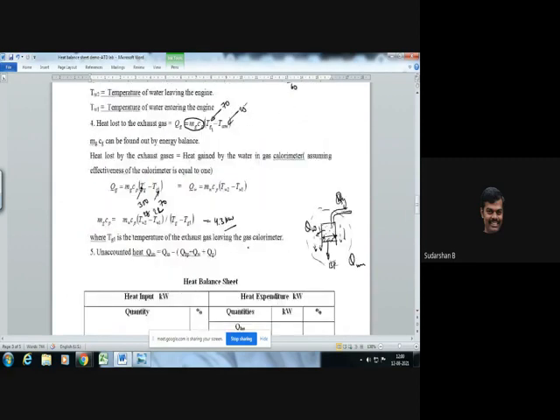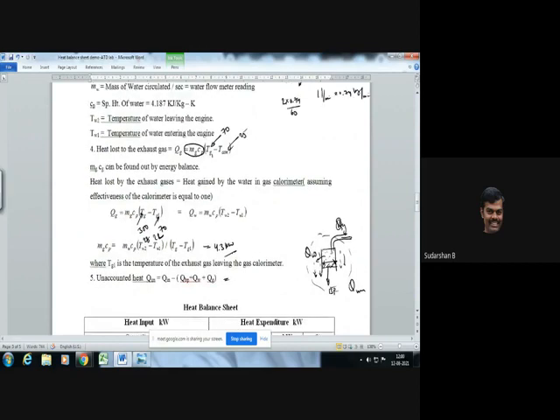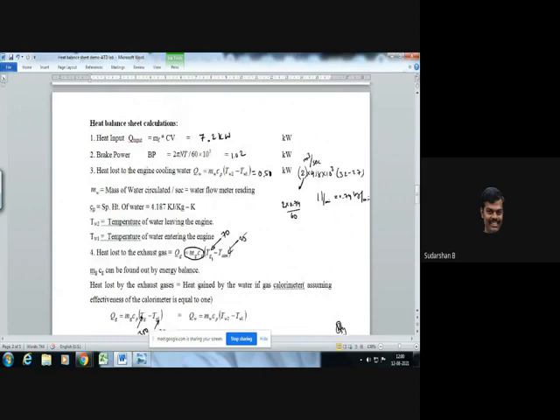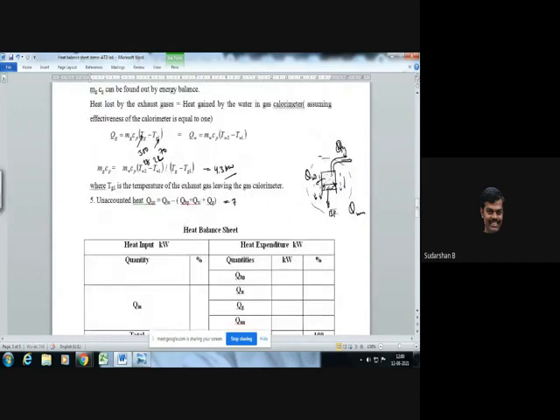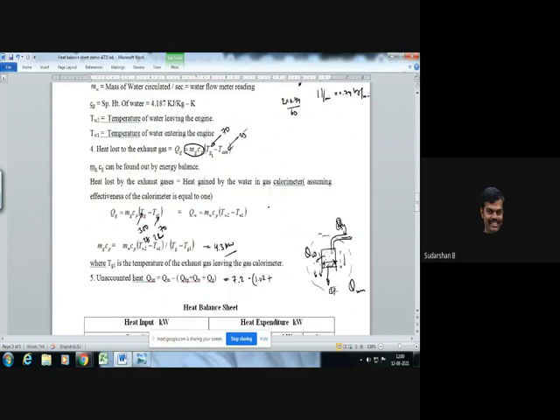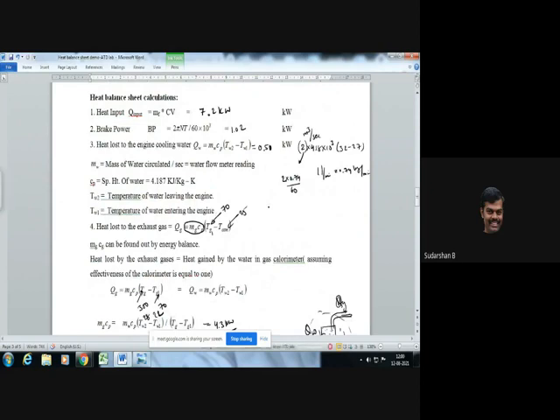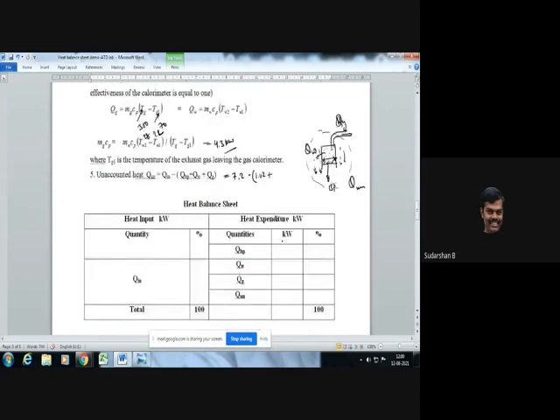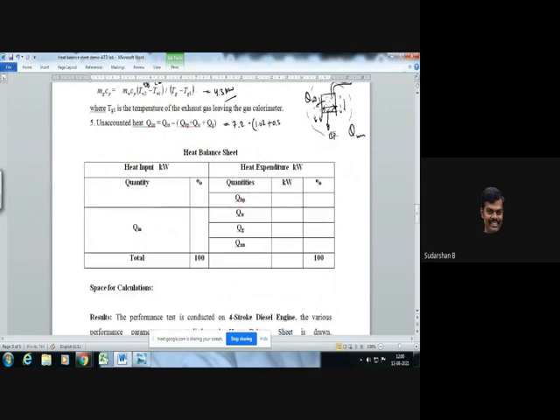Now unaccounted heat: take total heat input 7.2, minus BP which is 1.02, plus water lost which is 0.51, plus 4.3. If you do this: 7.2 minus (1.02 plus 0.51 plus 4.3), you get 1.37 as unaccounted heat.